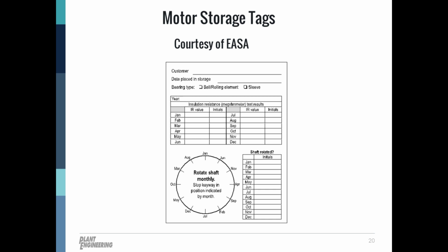All right. So this may be a little small here, but let's look at a few steps to take when moving forward with eliminating problems that may be encountered with our motor during the storage process. So I think this is one that gets overlooked sometimes. Here you will see a motor storage tag, courtesy of EASA, to give us a great guideline on the data that we should be taking monthly on our stored motors.